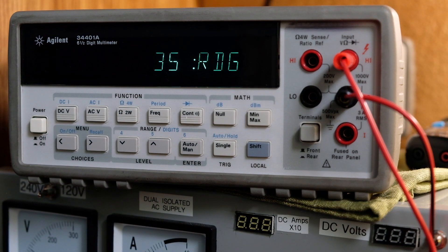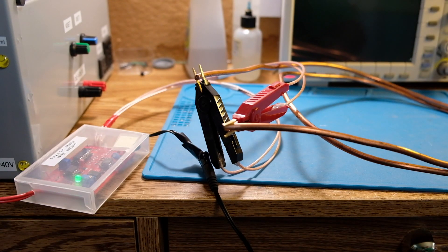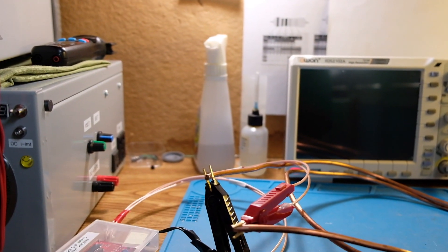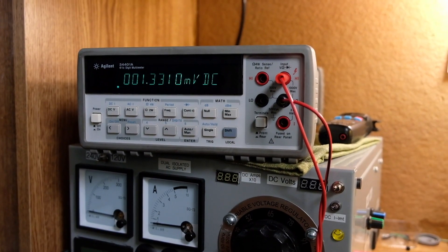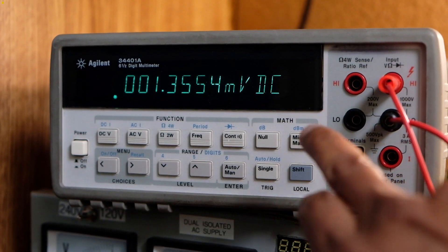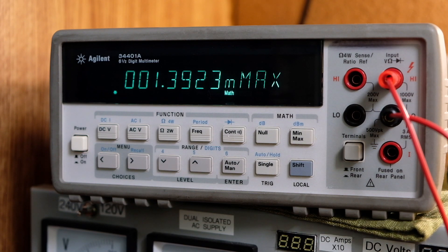Here's the Kelvin clamps now connected to the two ends of this copper wire. And now I'll start taking the readings on the meter. I'm doing a slow six-digit measurement, that's about 100 power line cycles. So that will give me a fair amount of averaging.